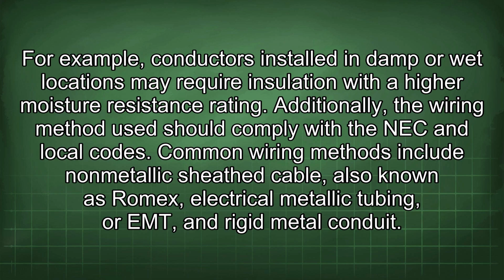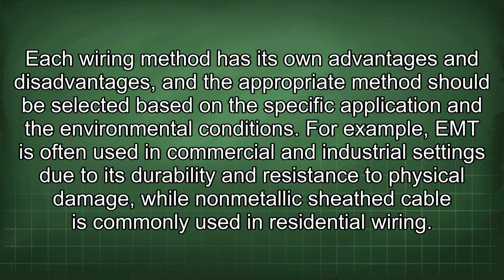Additionally, the wiring methods used should comply with the NEC and local codes. Common wiring methods include non-metallic sheath cable, also known as Romex, electrical metallic tubing, or EMT, and rigid metal conduit. Each wiring method has its own advantages and disadvantages, and the appropriate method should be selected based on the specific application and the environmental conditions. For example, EMT is often used in commercial and industrial settings due to its durability and resistance to physical damage, while non-metallic sheath cable is commonly used in residential wiring.